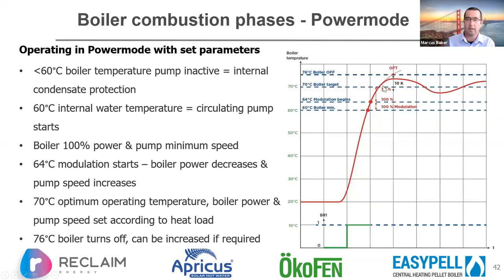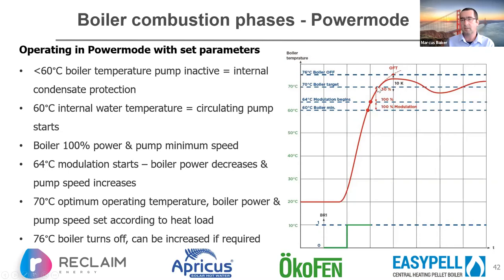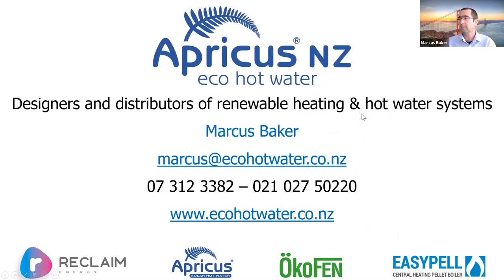We've done a lot of work on retrofit systems wanting to hold a nice consistent temperature, but in New Zealand's temperate climate the boiler sometimes thinks less heat is needed when the building is badly insulated. If a boiler is capable of very rapid and dynamic modulation, you get a really nice smooth flat curve — flattening the curve. If it's not capable of such smooth modulation, that's where buffering comes in to smooth it off. And that's me done on boiler controls.